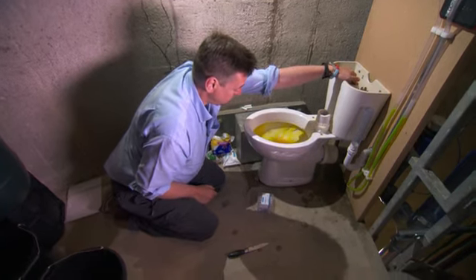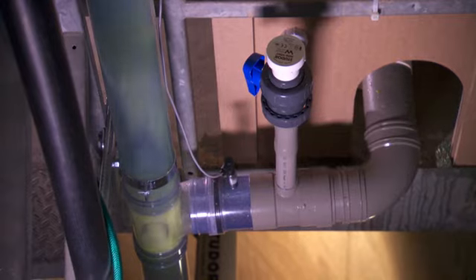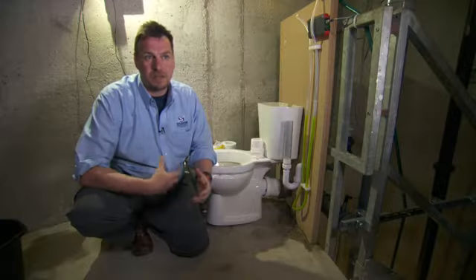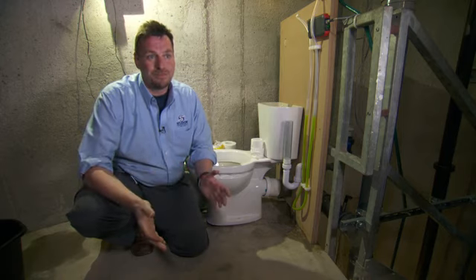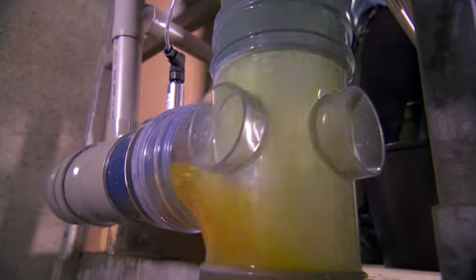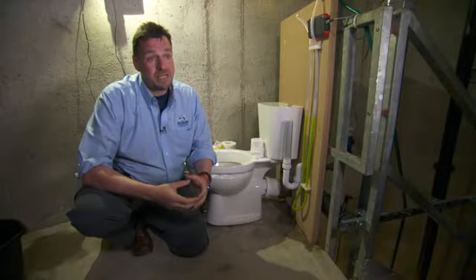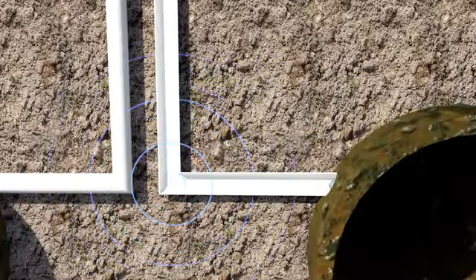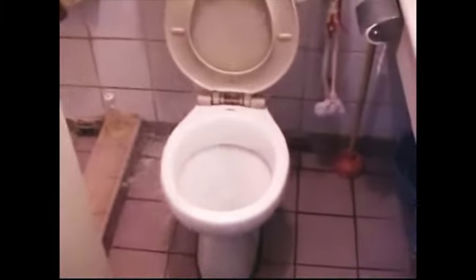They're doing this because 100-year-old building codes are failing in more and more modern high-rises. Everyone thinks that waste flows downhill, but in reality, with the drainage system, it's 20% solids to liquid and 80% air. When all that air and waste hit the ground floor, the waste goes to the sewer, but the air needs to travel somewhere. Big problems arise when that air isn't vented properly.